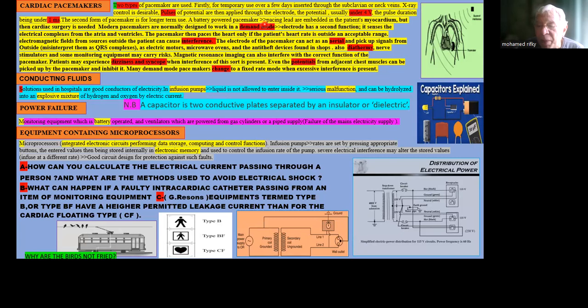Sometimes a patient with a pacemaker is admitted to the operative theater. He goes to the cardiac specialist, who changes this from demand type to fixed type, which is not affected by diathermy. So whenever I have a pacemaker, I ought to use what we call the bipolar, not the monopolar, so that it will not induce a deceiving electromagnetic wave for this electrode, because this electrode acts at that time as an aerial—it receives electromagnetic waves.